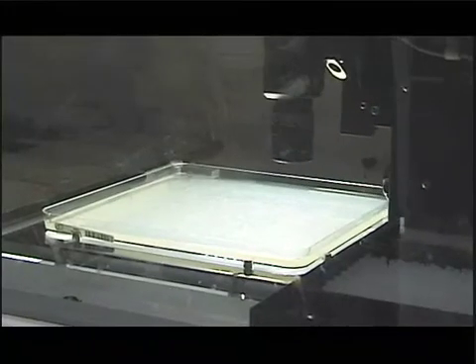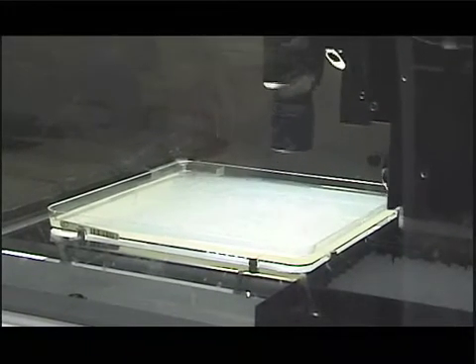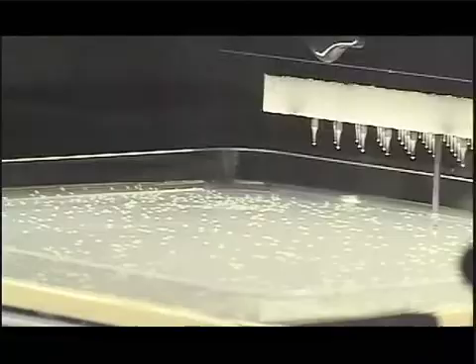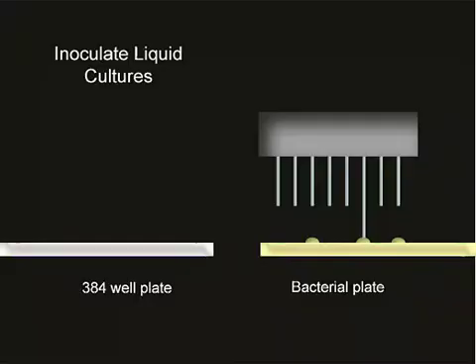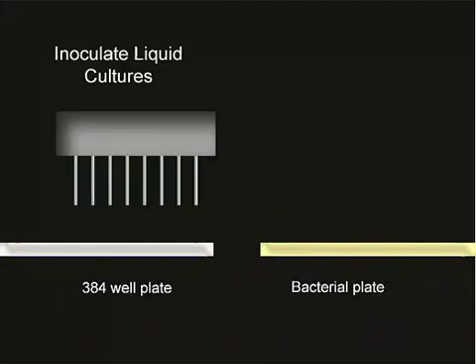The machine will then scan each of the plates and look for nice, uniform, isolated colonies. The 96 needle robotic arm will then pick these colonies, place them into glycerol and growth media that are contained in the 384 well plates.